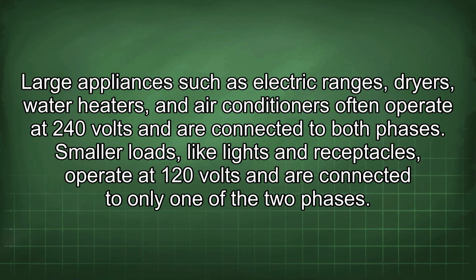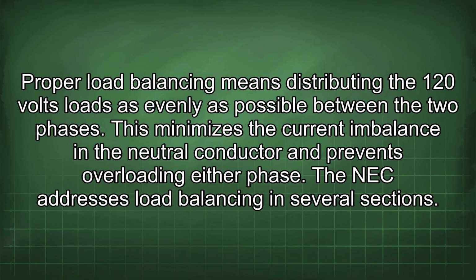Large appliances such as electric ranges, dryers, water heaters, and air conditioners often operate at 240 volts and are connected to both phases. Smaller loads, like lights and receptacles, operate at 120 volts and are connected to only one of the two phases. Proper load balancing means distributing the 120 volt loads as evenly as possible between the two phases. This minimizes the current imbalance in the neutral conductor and prevents overloading either phase.